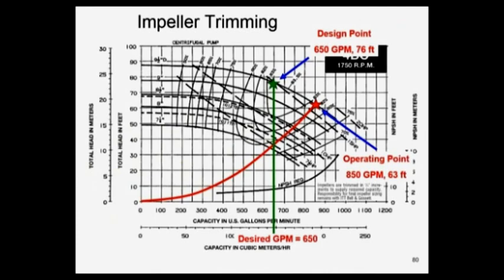And it crosses, help me out there, somewhere about 7.5 inches, something like that, maybe a little less. We'll figure out exactly in a minute. But that's the new impeller size that we need. Look at the horsepower. The horsepower is down a little bit over 7.5. Wow!